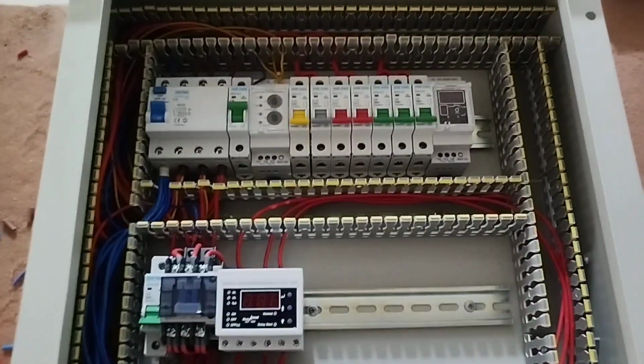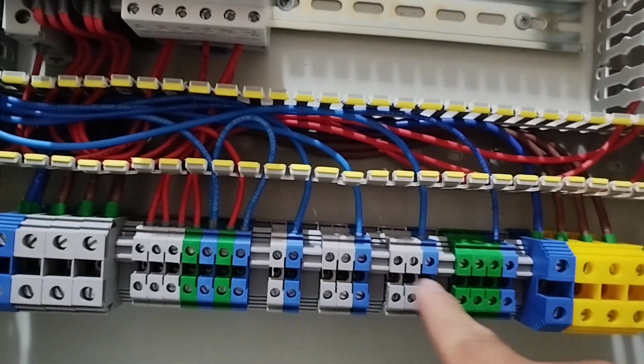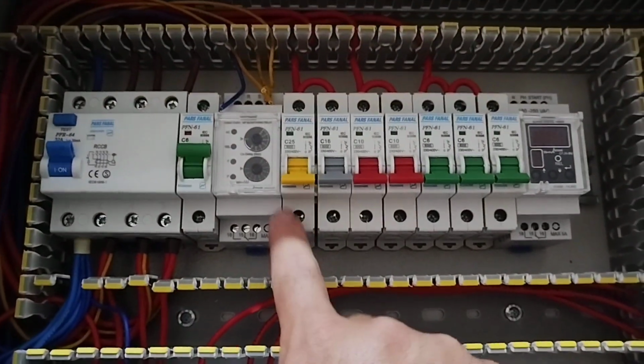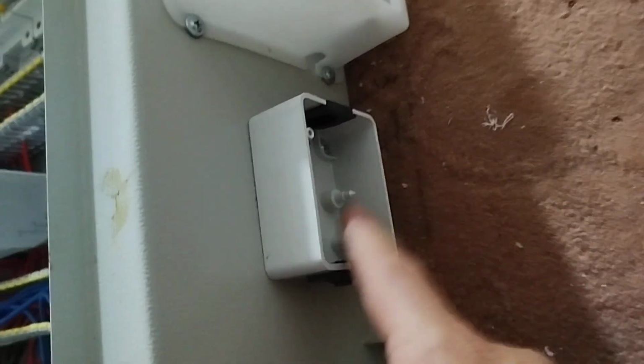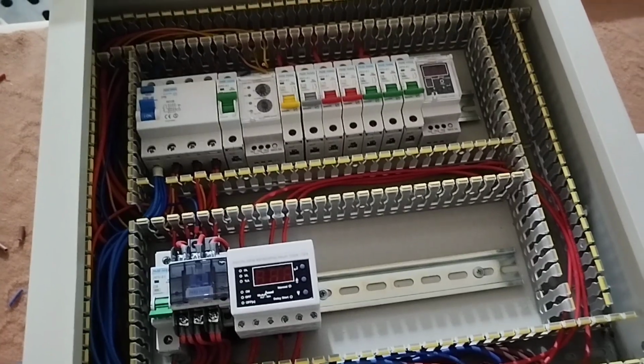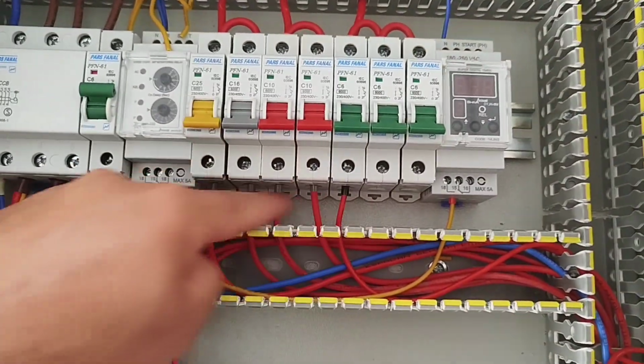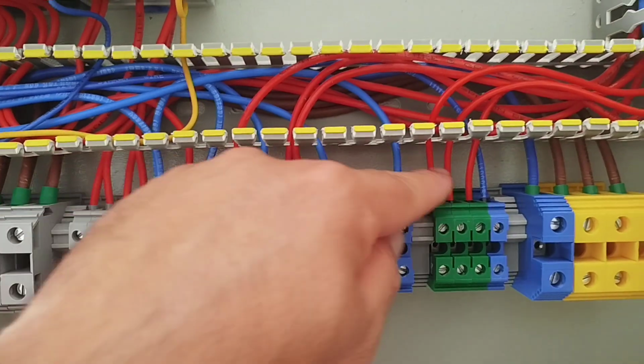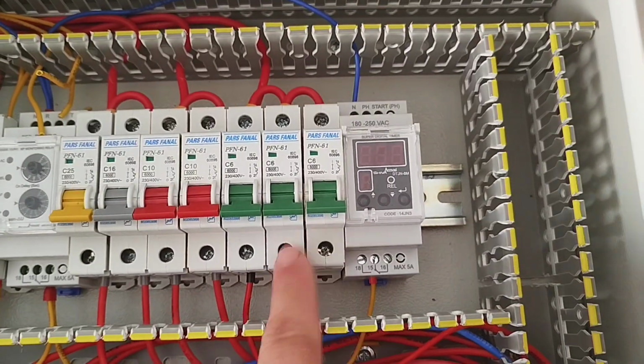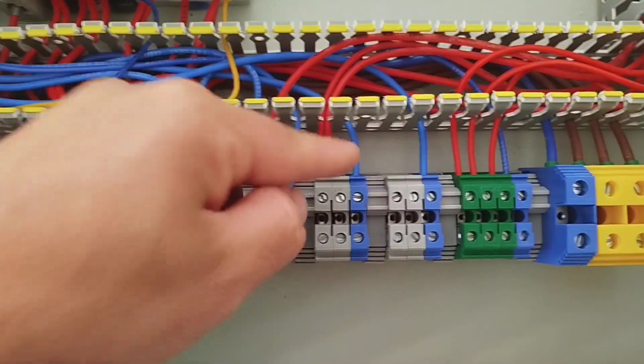In this step, we connect the phase wire from the output of the miniature switch to the single-phase output terminals. This miniature switch is for the outlet that is installed in the body of the electrical panel. Two of the single-phase outputs are controlled by the selector switches installed on the electrical panel door. So we connect the output of the miniature switch to the input of the selector switch and their output to the output terminals.